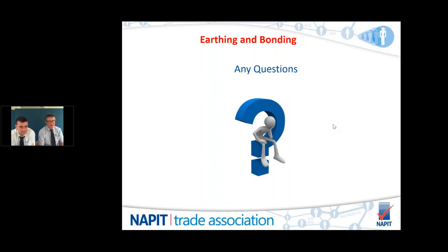The regs also state additions and alterations. And with those additions and alterations to a circuit, what it states basically is that the system that you're going to expand and add to has to be compatible. And if required, then the earthing system has to be adequate as well. It doesn't actually state what adequate is. You would have to take into consideration whether you thought a 6mm bond would do the job and disconnect the protective device in the right time without any damage to that protective conductor.